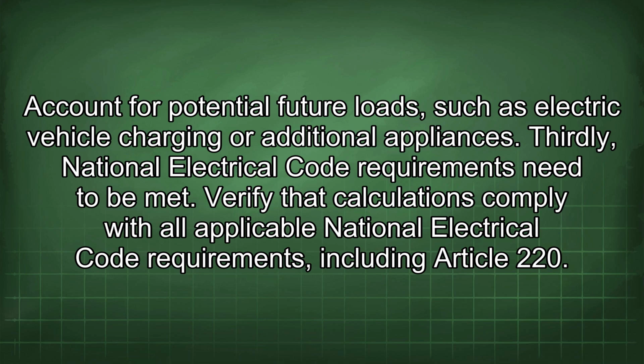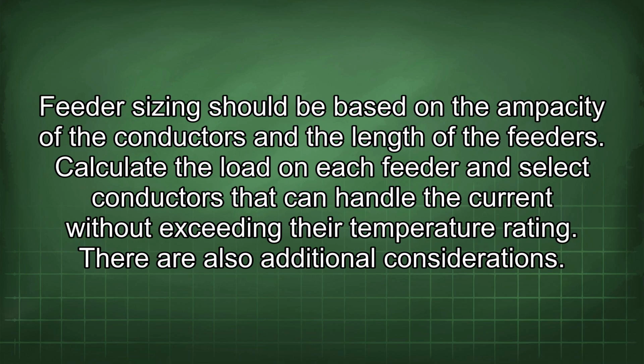Thirdly, National Electrical Code requirements need to be met. Verify that calculations comply with all applicable National Electrical Code requirements, including Article 220. Feeder sizing should be based on the ampacity of the conductors and the length of the feeders. Calculate the load on each feeder and select conductors that can handle the current without exceeding their temperature rating. There are also additional considerations.